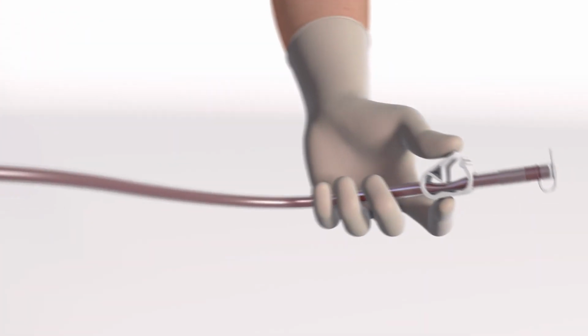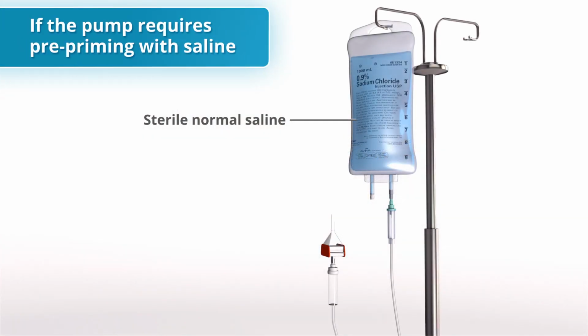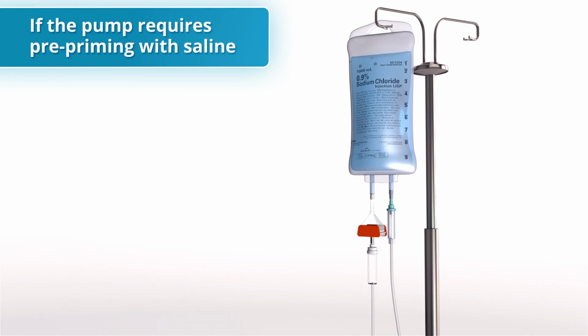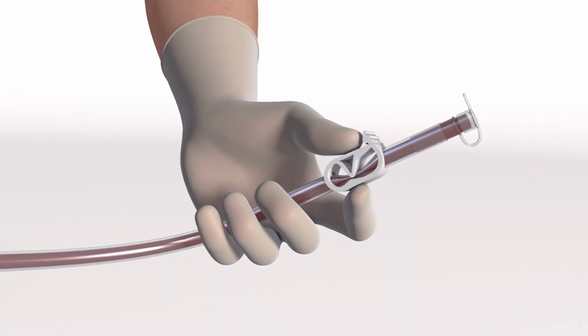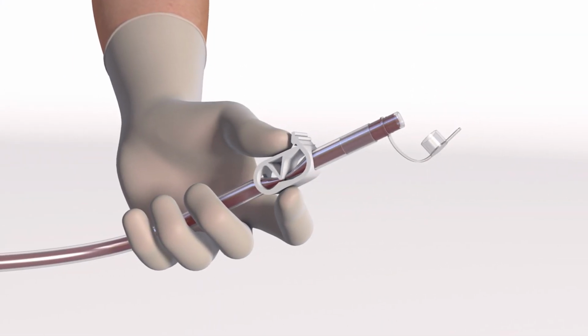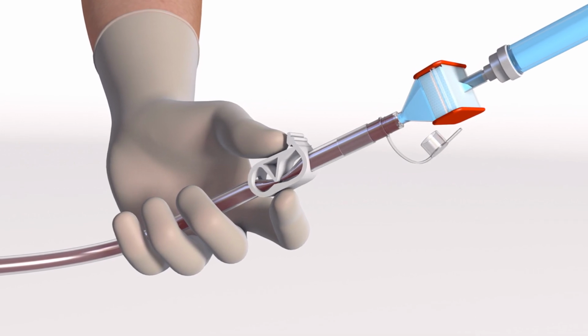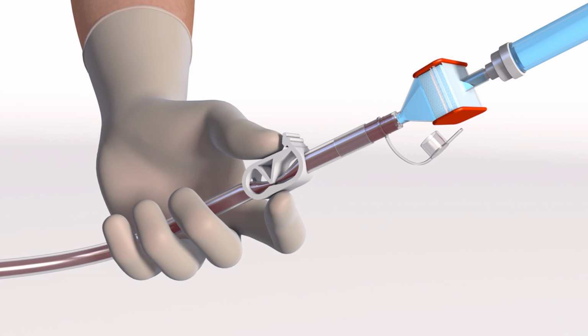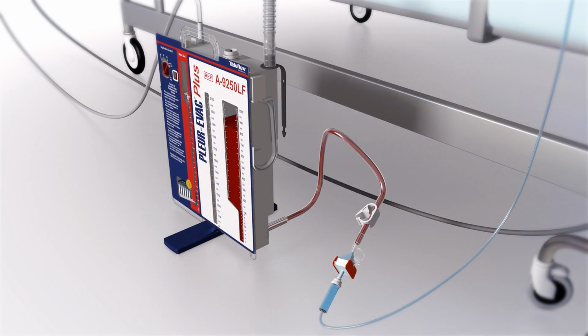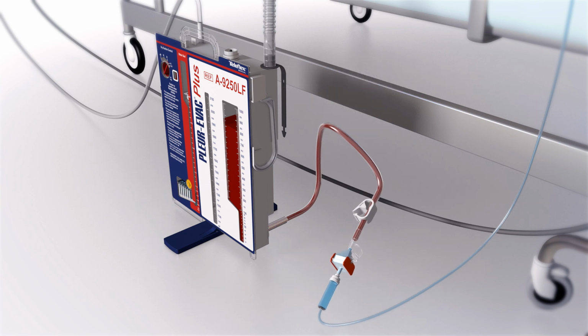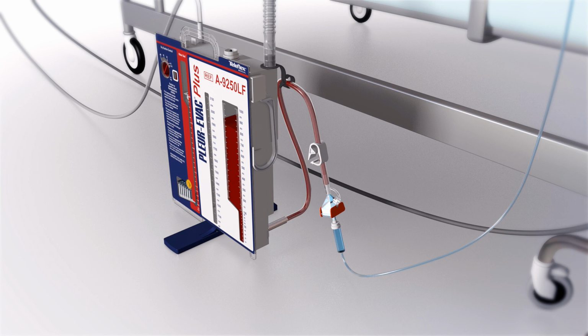Now, close the clamp to temporarily stop blood flow. If the pump requires pre-priming of the microaggregate filter and administration set with saline, do so per the manufacturer's guidelines. Remove the tethered cap from the exit port of the tubing and spike it with the saline-primed microaggregate filter and administration set. Open the reinfusion tubing clamp. The A9250LF contains a tubing placement strap at the top of the anti-kink tubing. Using the provided strap, position the reinfusion line, ensuring the microaggregate filter is in a spike-up orientation. Reconfirm the infusion line is filled with blood and free of air prior to beginning reinfusion.